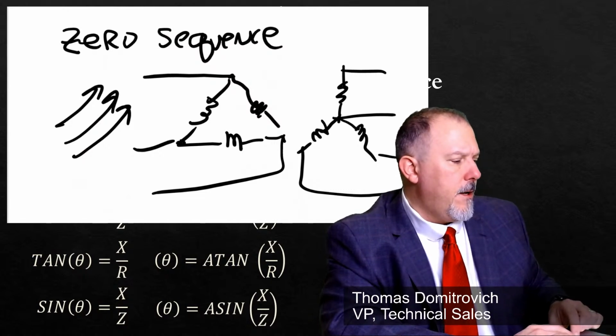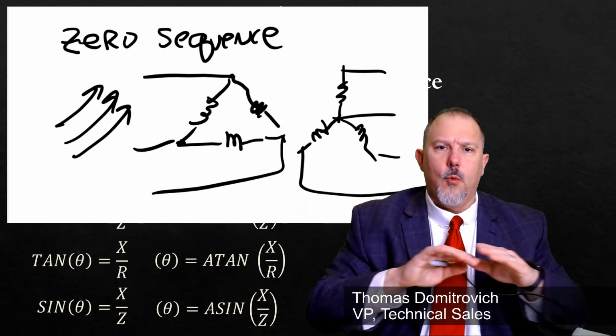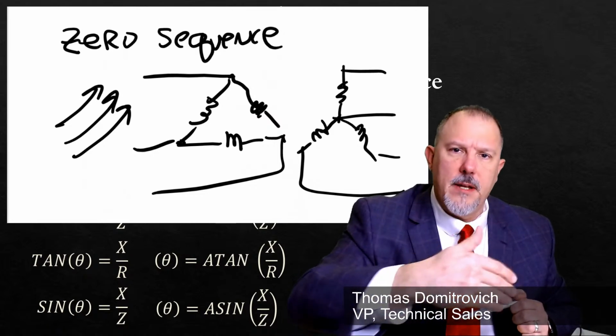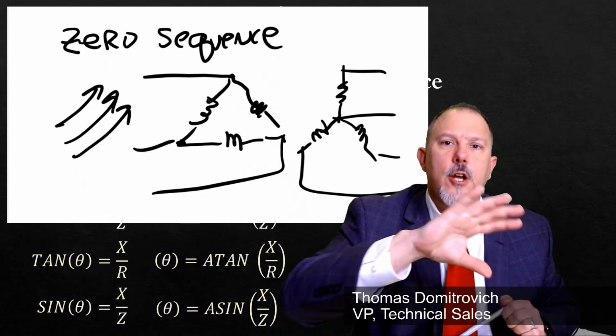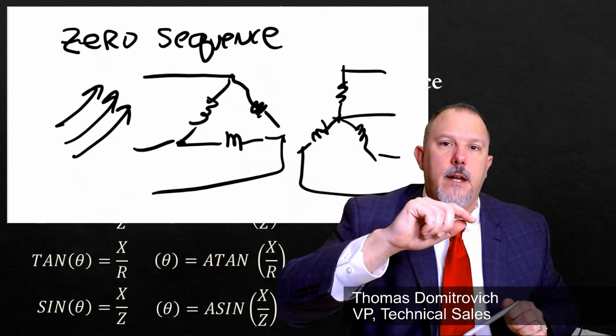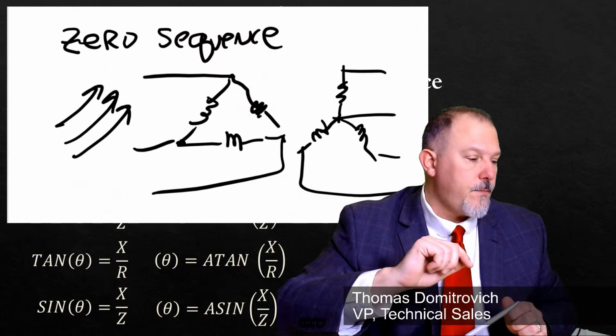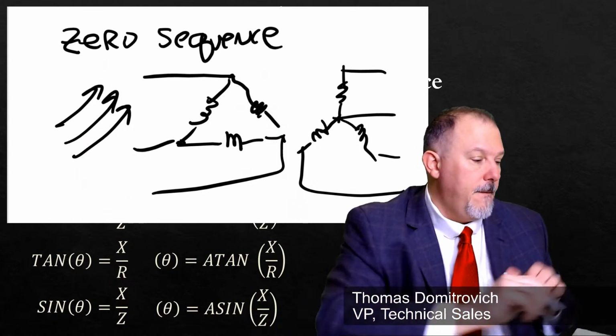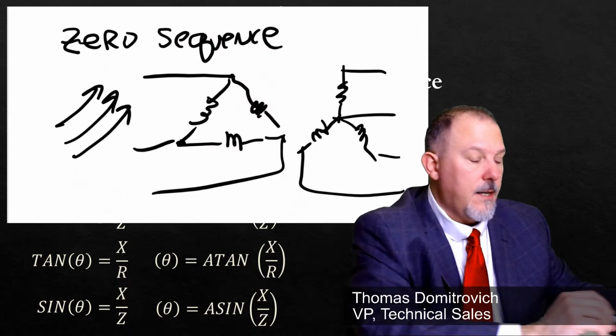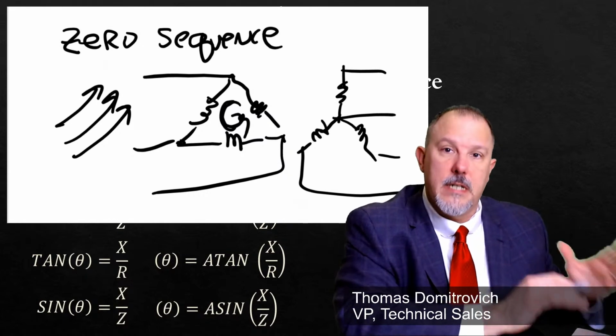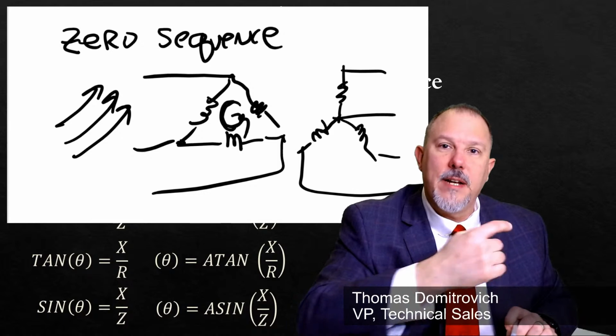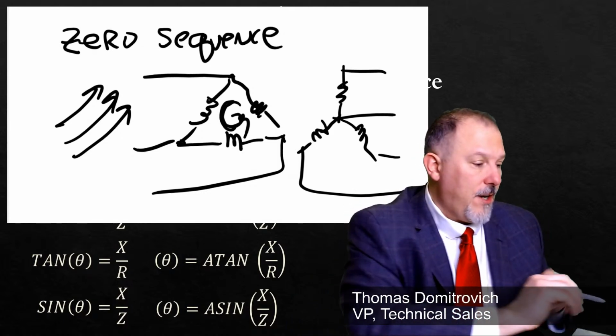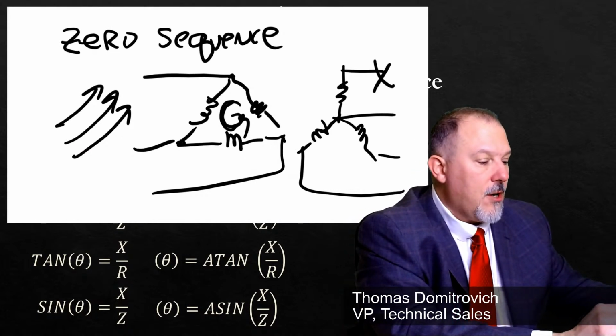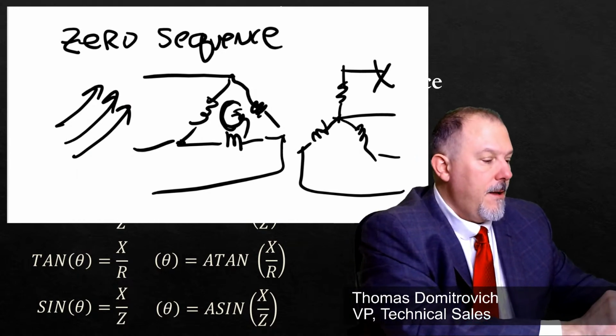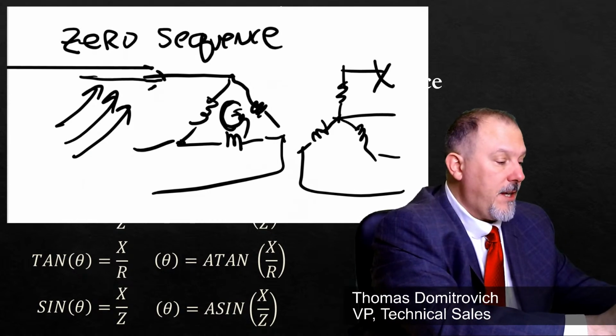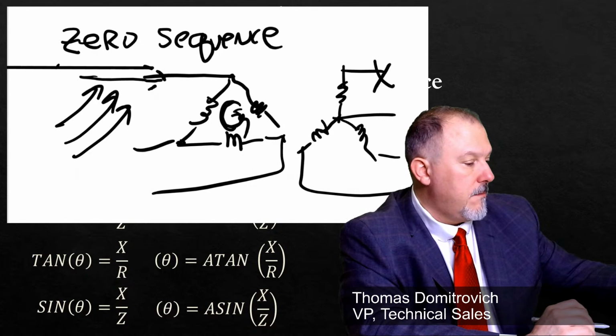So when you look at the way you do your additions, we already know that A, B, and C positive sequence are 120 degrees apart, negative sequence 120 degrees apart, and then your zero sequence, they're all in phase with each other. We know that because of that, your zero sequence currents are going to circulate in this delta because they're not going to be able to go through the delta. Now, that doesn't mean that you're not going to have short circuit current on the line side of this transformer. So if I have a fault down here to ground, because the zero sequence currents won't flow through the delta, that doesn't mean I don't have any current being contributed from the upstream circuit system. It just means that...